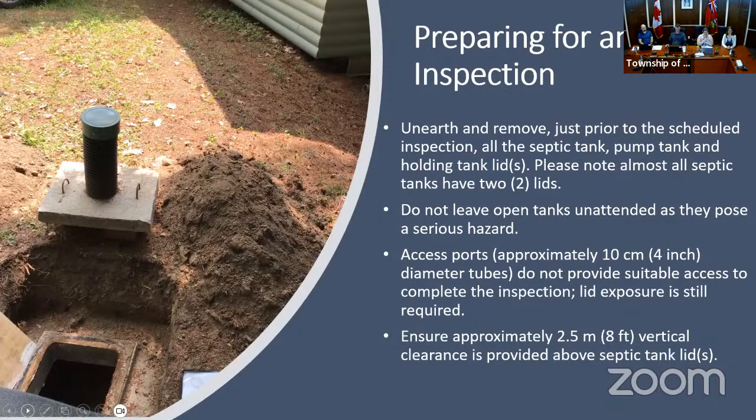So continuing on how to prepare for the inspection, because this is a phase 2 inspection, so we are, let's call it, a more intrusive inspection. That does mean that we need to see inside of all of the tankage on the property. We have been talking a lot about septic tanks. However, a lot of sewage systems may have a pump tank. As long as the pump is outside of the building, so it may be before your septic tank or after your septic tank, we would like to be seeing that pump as well as part of the inspection, both for condition of tank, but function of pump.